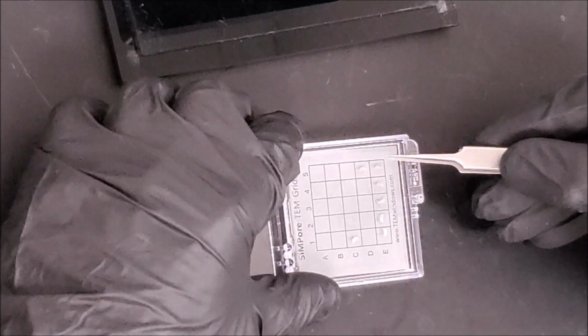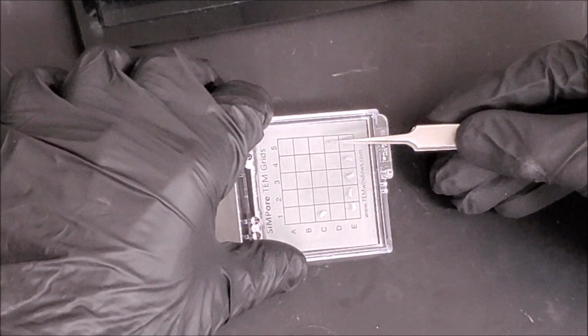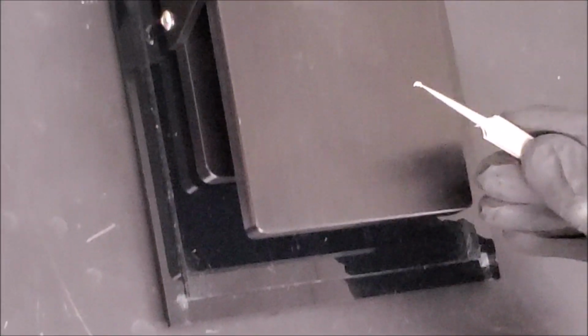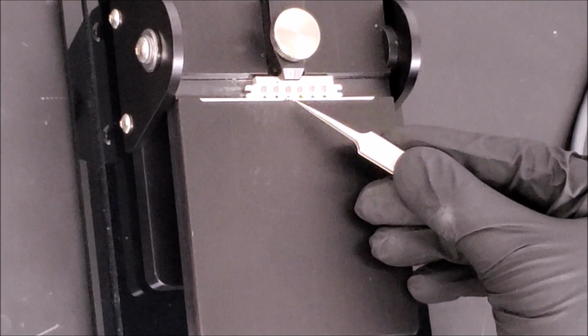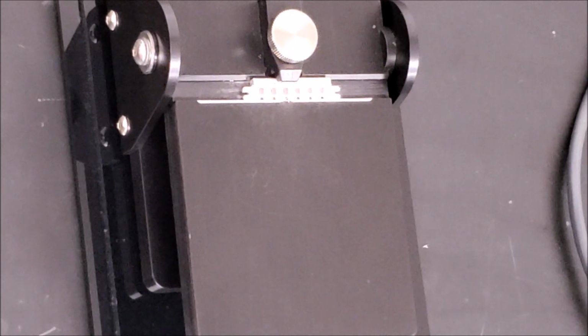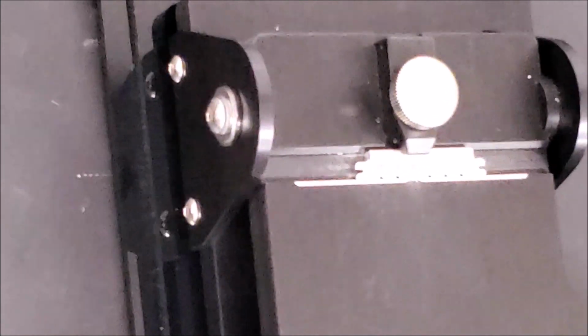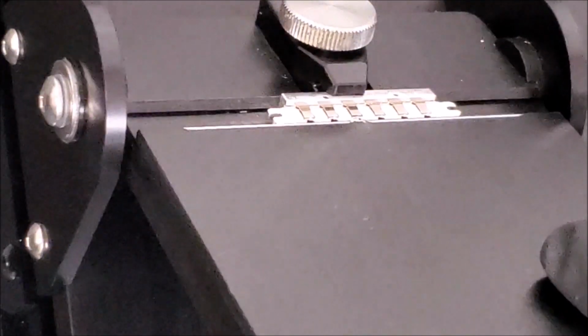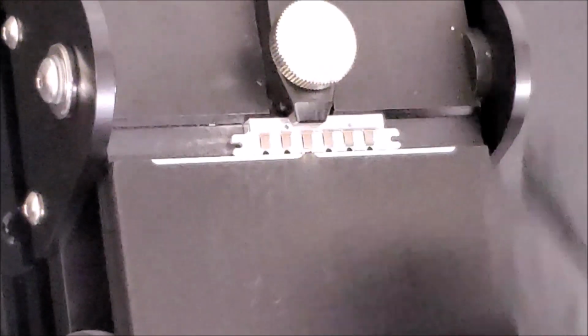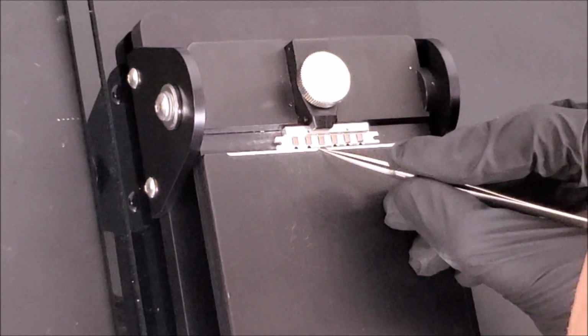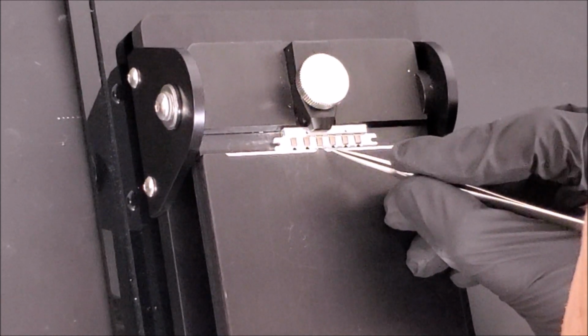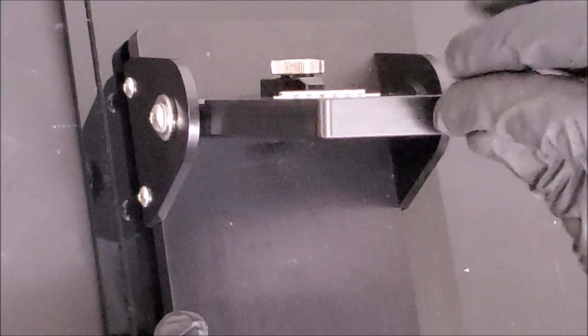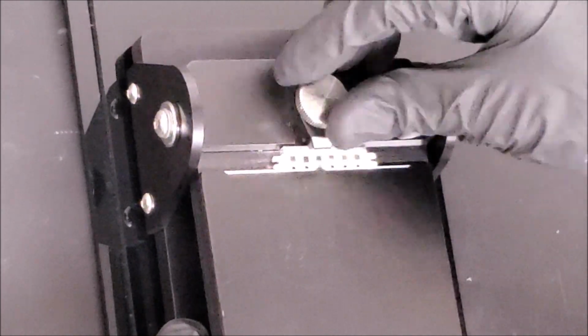Use a sharp pair of tweezers or a set of vacuum tweezers to pick up an Omniprobe grid for loading into the holder. Note which side of the grid is rounded, as that is the side that should be entered into the holder. Place the grid just in front of the clip. Then tilt up the base on the loader and gently tap on the edge, and the grid should slide under the clip. Then tilt the base of the holder back down and check to see if the grid is sitting level inside of the holder. If not, use a sharp pair of tweezers to carefully reorient it so it is level. Then remove the grid holder from the loader.